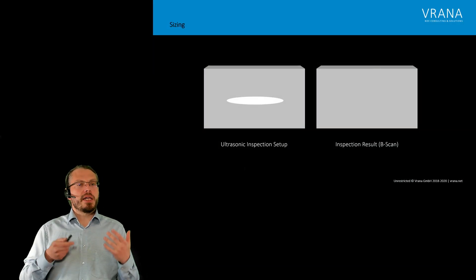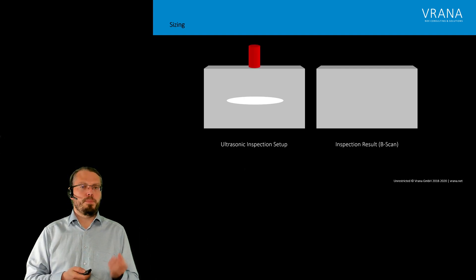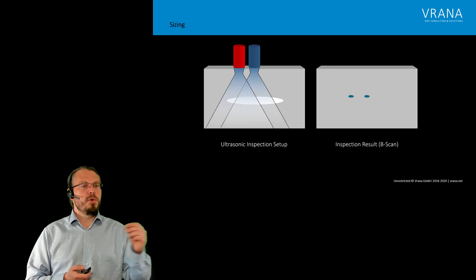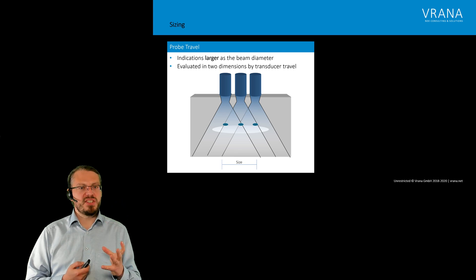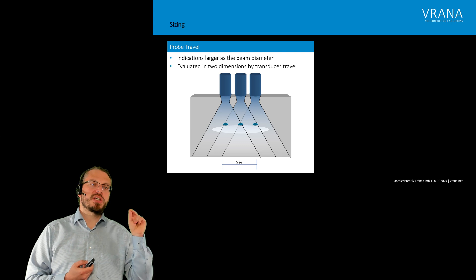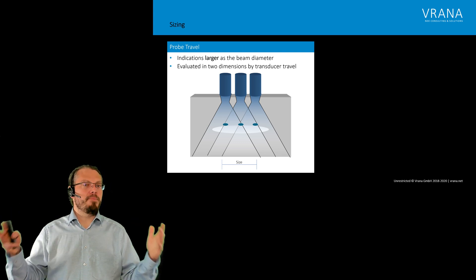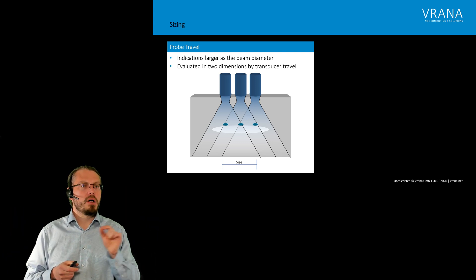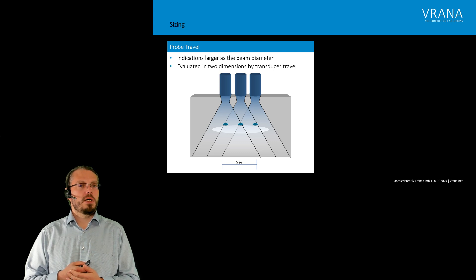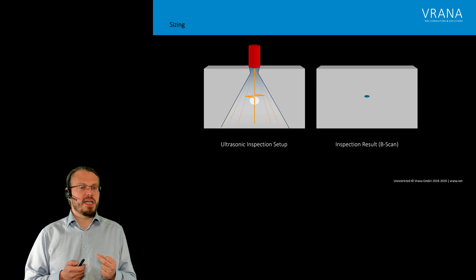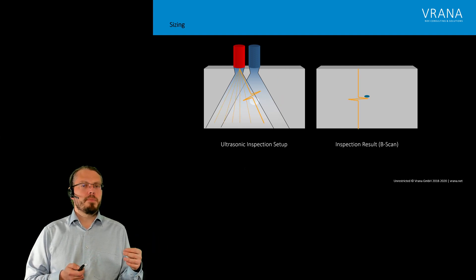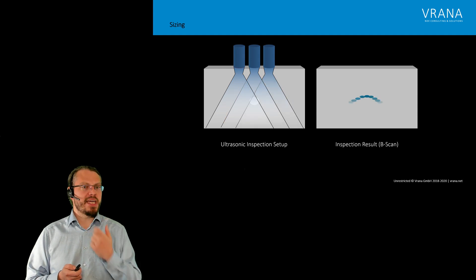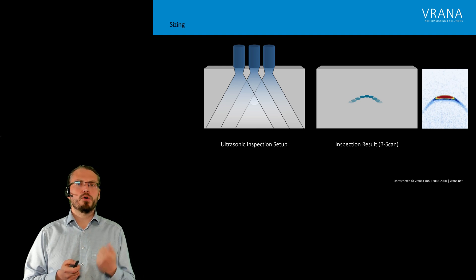If we are doing an ultrasonic inspection and we find an indication — we put our probe on the component, find the indication, move our probe — we see that indication has a certain size. That kind of sizing works only if the indication is larger, actually much larger, than our beam diameter, and we can use it to get our size in two dimensions. Now what do we do if we have a smaller indication? We will see it on our A-scan, but once we start moving our probe we get a very different shape.